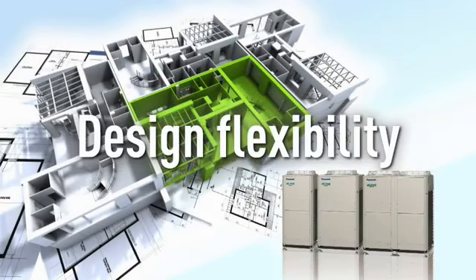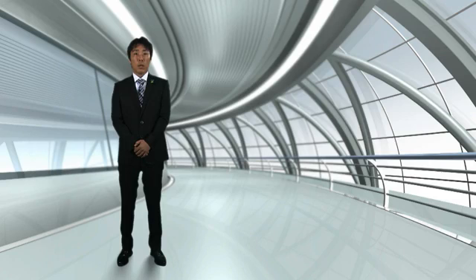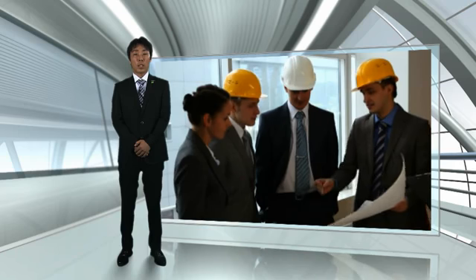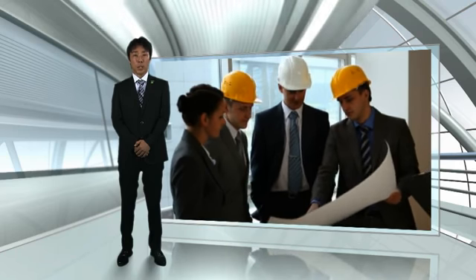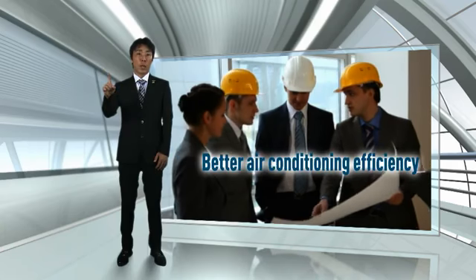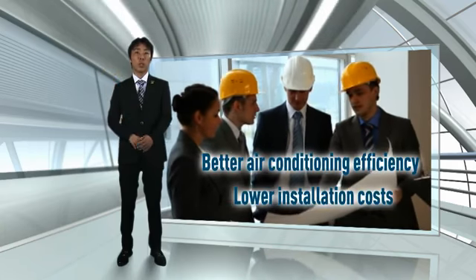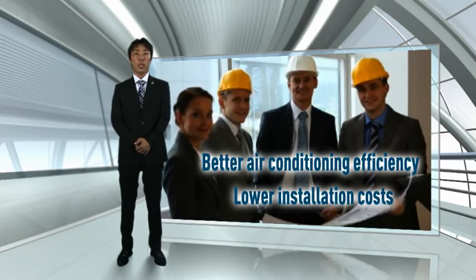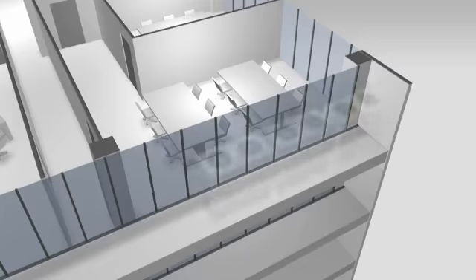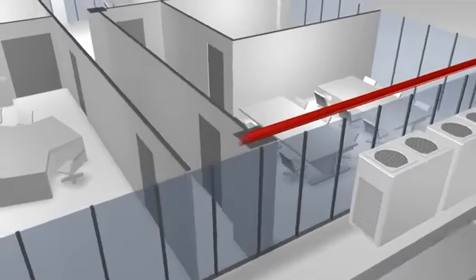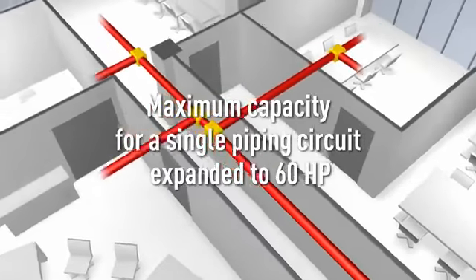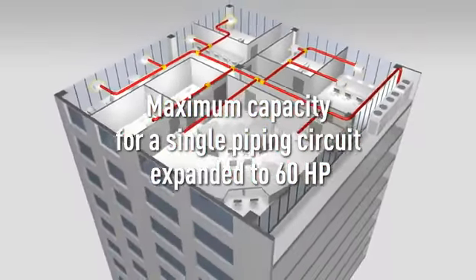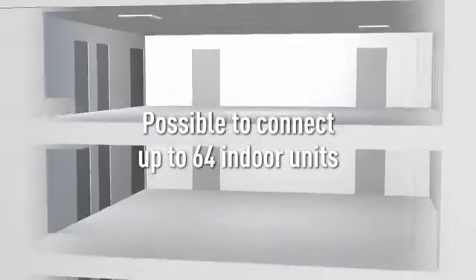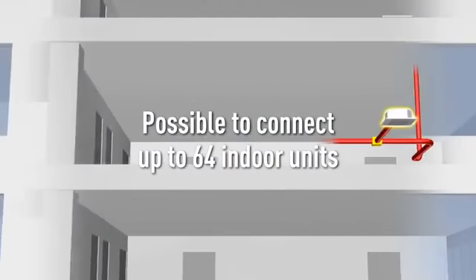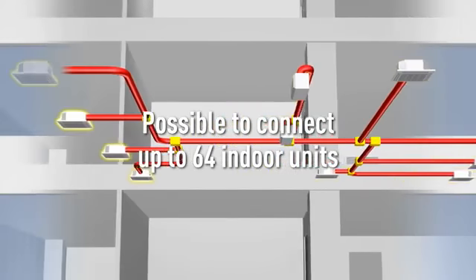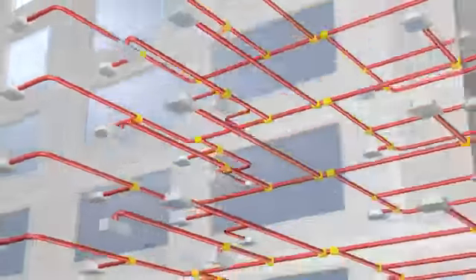Next, let's look at design flexibility. We interviewed building designers and architects about requirements and ideas they might have. The result was that we discovered design flexibility to be an important key to better air conditioning efficiency and lower installation costs. First, we expanded the maximum capacity for a single piping circuit to 60 horsepower, and also made it possible to connect up to as many as 64 indoor units. This is effective for achieving a high-efficiency air conditioning system with lower installation costs.